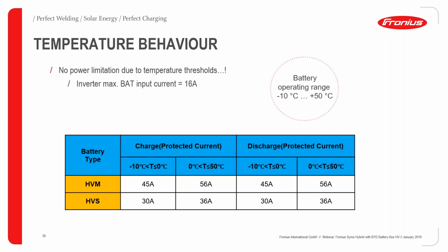In terms of temperature, with the last model there were some limitations with the B-Box HV — when you got down really cold, under 0 degrees, you had reduced power, and also in the hot range. That's technically the case from the battery side. The HVM, within the normal 0 to 50 range, has 56 amps, but in a lower range it's 45. However, because we're limiting at 16, there's no change in charge or discharge rates with the inverter at any of those temperatures.